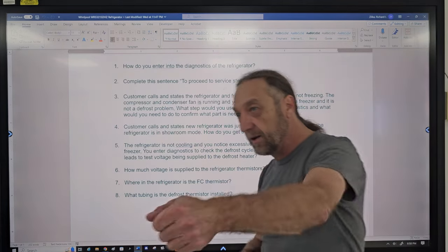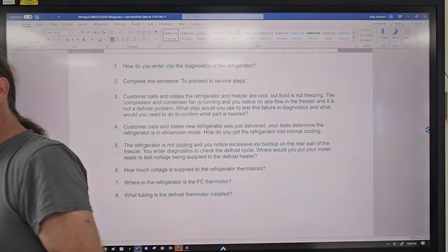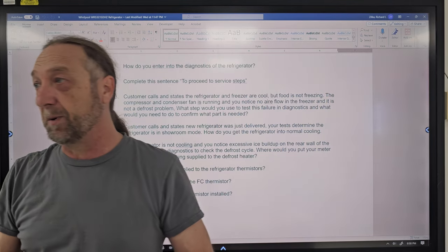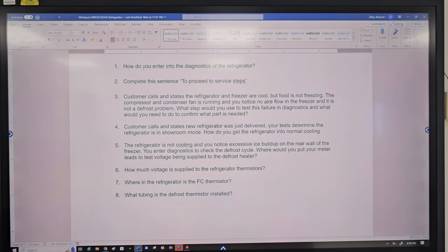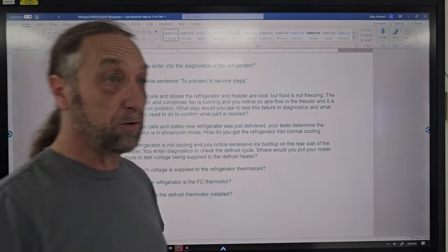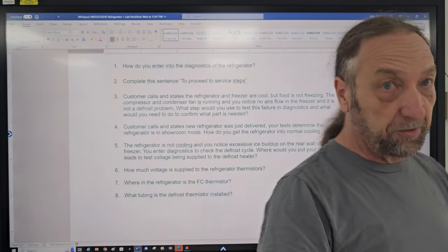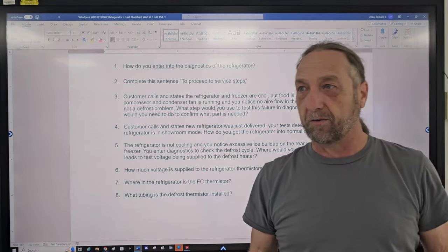But if customers are turning it on and off and playing with it too many times, it could damage components. But the other thing is that whenever it goes into cooling, it's going to remove the moisture inside the box and create frost on the evaporator. It's going to go into defrost.